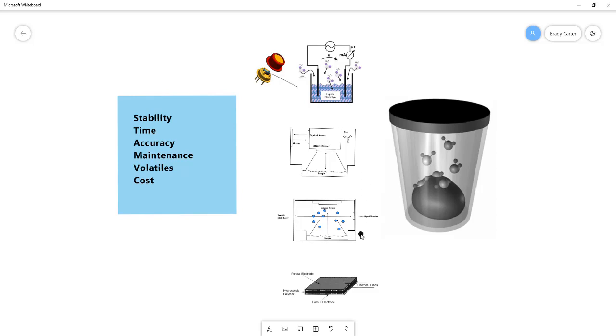So that means that the two electric property sensors tend to be more stable in that they aren't as affected by the user and potential contamination. That said, the hygroscopic polymer can be unstable when it goes through successive wetting and drying periods. Because when the polymer is subjected to high relative humidity, it absorbs a lot of that water, and it continues to drift. And then when you go back down to lower water activities, it tends to read high. So that can affect its stability. In terms of analysis time, the thing that has to happen for a measurement to be taken, there are several steps.